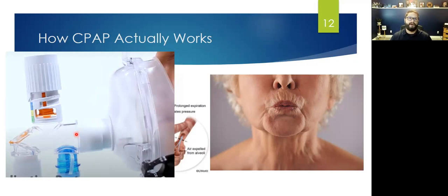This unit requires this exhalation valve, and there's a spring inside this that you create additional tension on. And what's neat is you'll notice your system, unlike most other systems, does not require a manometer, which is obviously going to measure that pressure, because it doesn't need to. Each one of these units, every single one of them that comes off a line, they test this thing to make sure that the spring tension is exactly what it needs to be at each of those steps of the process, so that we know we're giving the right amount of PEEP. So really cool. One less thing for us to have to focus on when we're trying to deal with everything else and determine what meds we're going to give and what other treatments we're going to do and if we're getting lines going and all those kind of things. So you'll also see there's an inline integrated neb into this system, which is pretty cool. No more T pieces, anything like that.